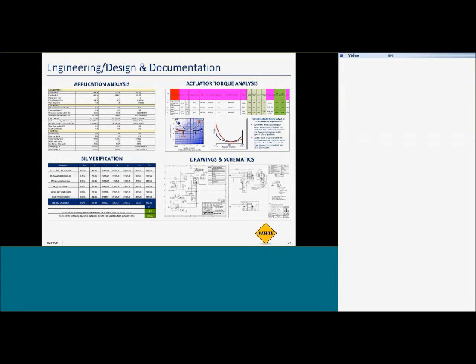On the top left here, this is an application lifecycle analysis that we do for the Vanessa triple offset. This is a sizing program that we have that takes a look at the process conditions and determines: do we have too much noise across this valve? What are the torques truly going to be for this valve in this application? This is very critical for all valve applications in SIS. We're talking about safety. We're talking about people's lives, and I think it's important to get involved with our customers at this level, doing a deeper dive application analysis, whether it's ball valves or triple offset valves or butterfly valves.